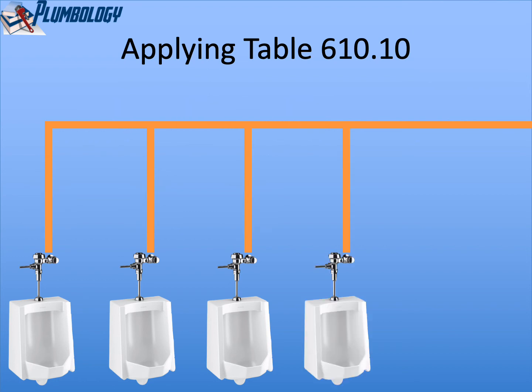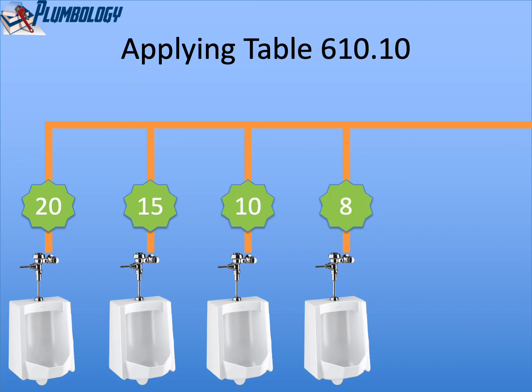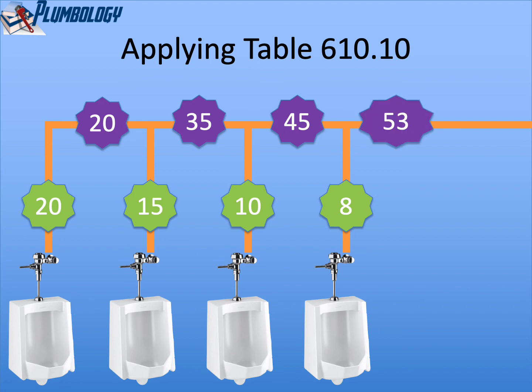If we have four urinal flush valves, we still start at 20, the next one is 15, then 10, and the fourth one will be 8. Going back to the pipe segments: 20, 35, 45, and 53. That water pipe branch would be sized for 53 water supply fixture units.